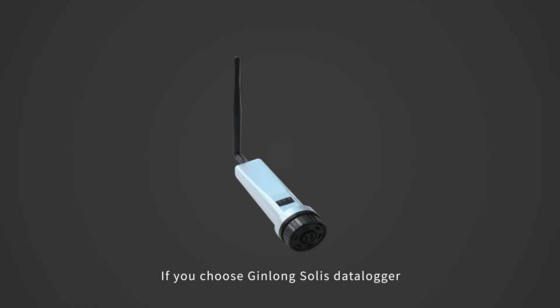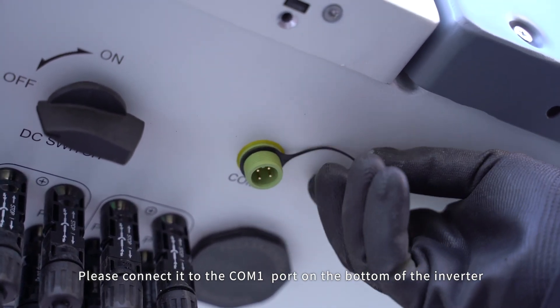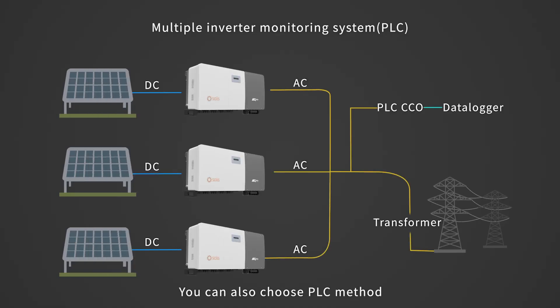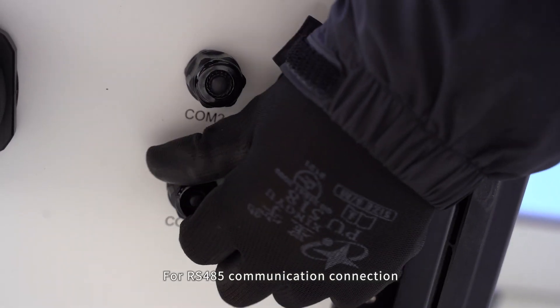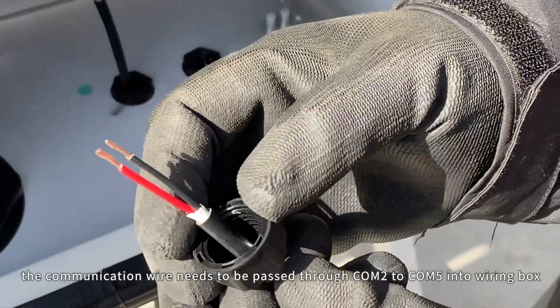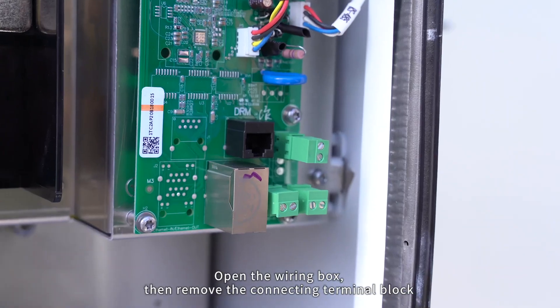Communication connection. If you choose Solis Datalogger, please connect it to the COM1 port on the bottom of the inverter. You can also choose PLC method or RS-485 daisy chain to configure the monitoring system. For RS-485 communication connection, the communication wire needs to be passed through COM2 to COM5 into the wiring box.